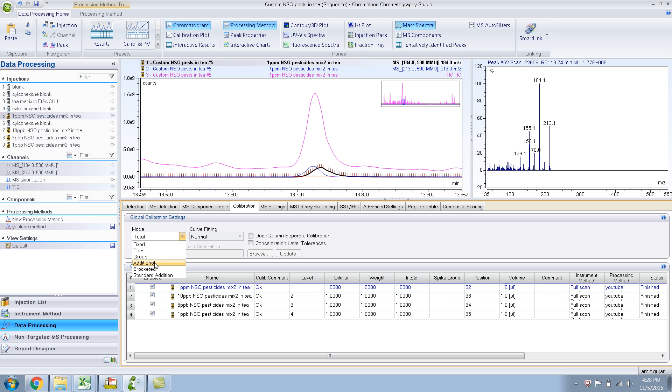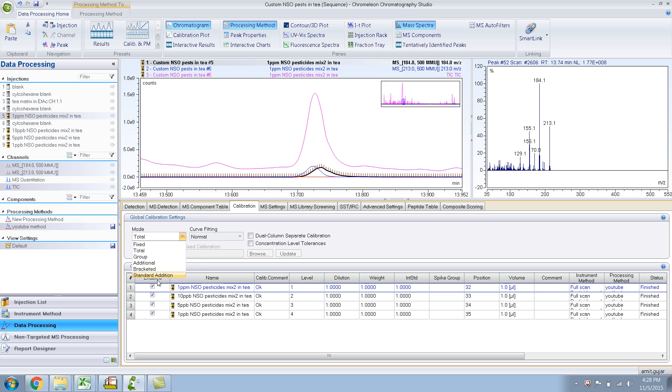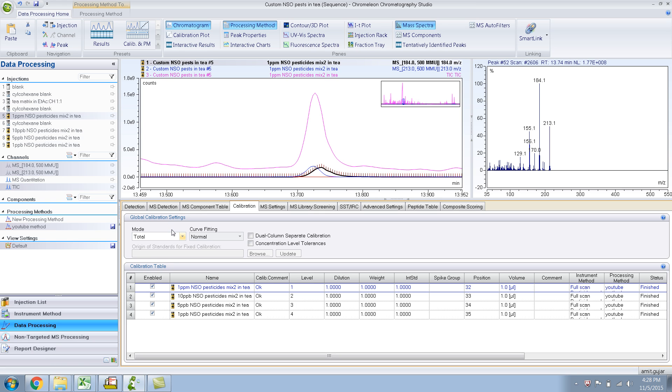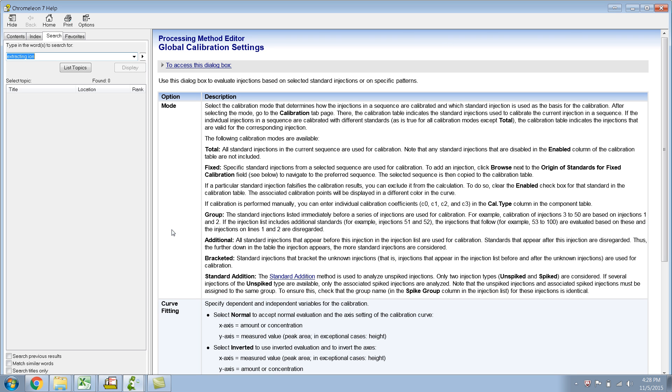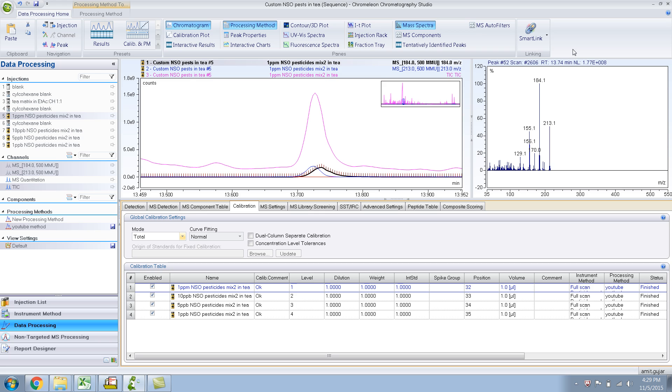Obviously there are other settings also and I haven't tried it personally, but you can read the help over here and find out what each of these does. Help is like F1. So if you click F1, there you go. It will show you the help related to calibration settings. So that's one good thing to remember. F1 is help.